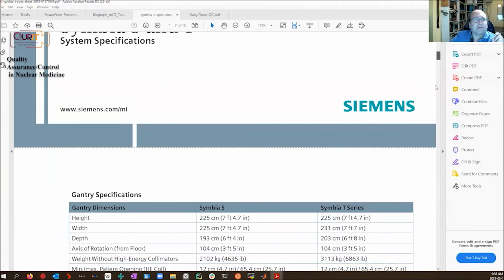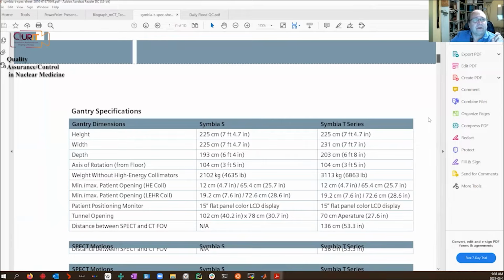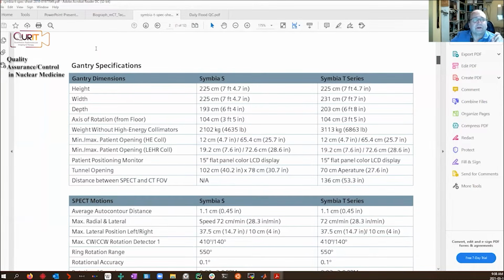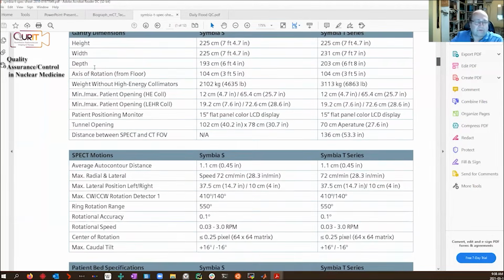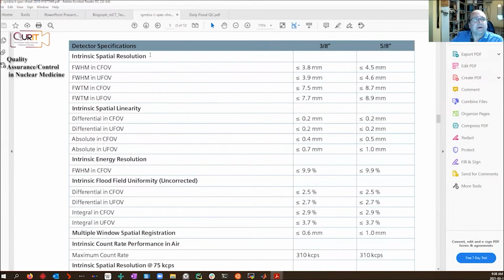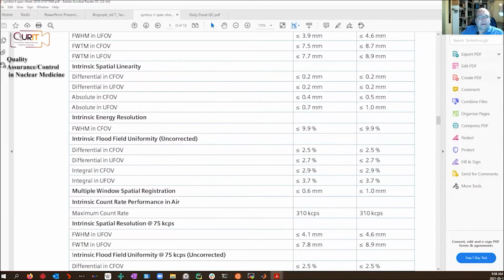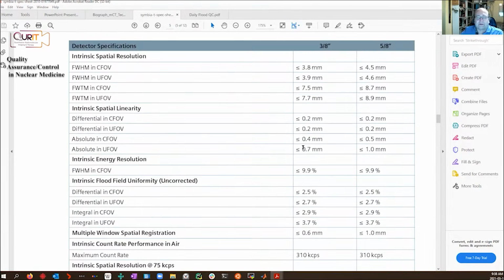But what we want are the numbers. So if we go down here from the design and look at the numbers, if we're interested in the performance of a SPECT camera, these are the numbers we're interested in. You see things like the intrinsic spatial resolution. These are the numbers they measured at their factory. And what is the intrinsic flood field uniformity, uncorrected and with the flood correction? What are all these numbers? They're all listed here. These values were measured at the factory.